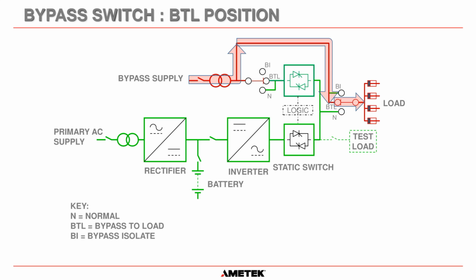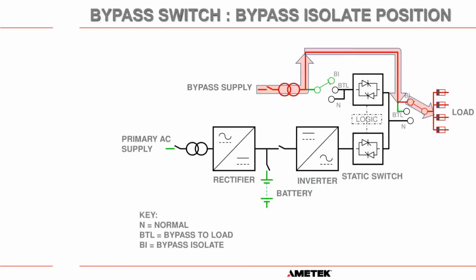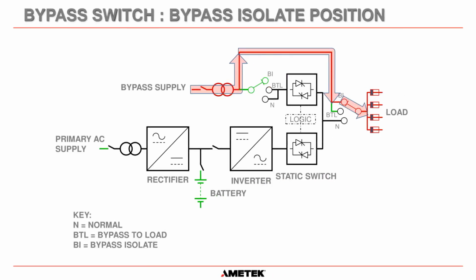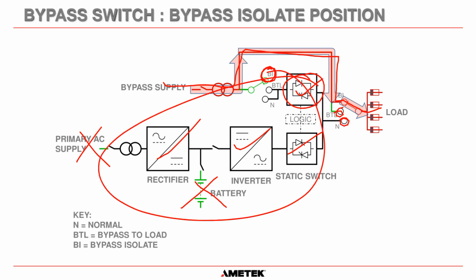And then the final position is bypass isolate. Let me just move it, this one here. Now you can see power flows out through the bypass isolate contact. So now it's not the bypass to load contact, it's not the normal contact. And you can see there is now no power going into this static switch. What that would allow you to do is have the primary AC power off. You could disconnect the battery and move the system into bypass isolate, and there is no power at the static switch or at the inverter or at the rectifier. And you could work on this system safely.